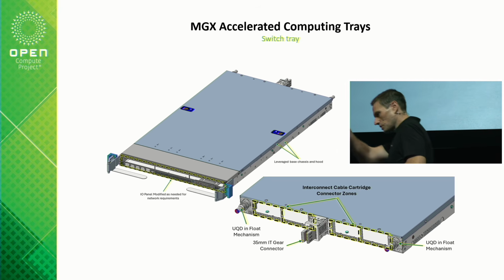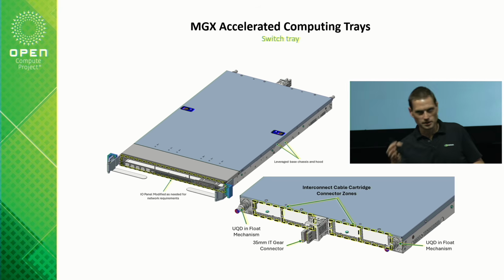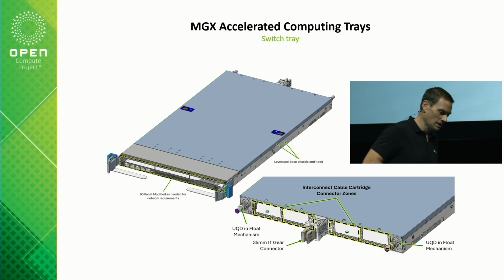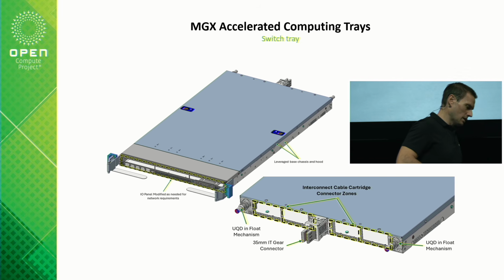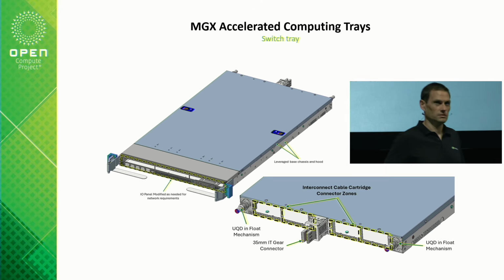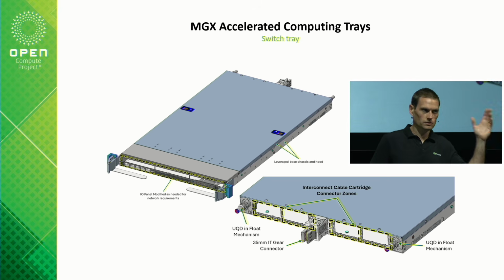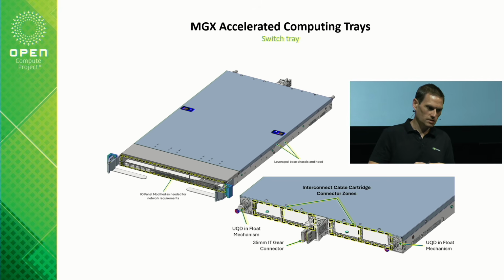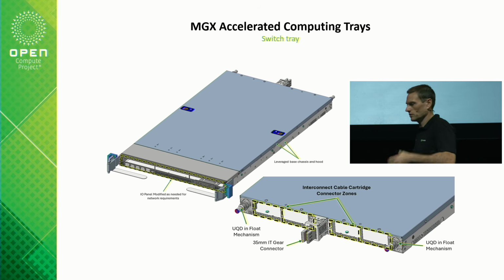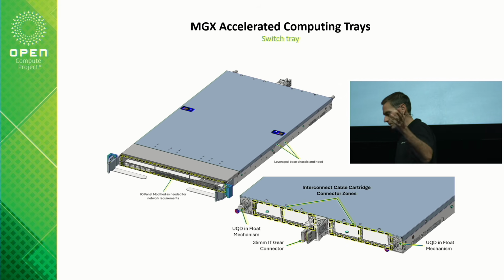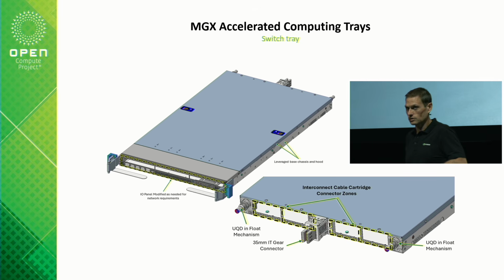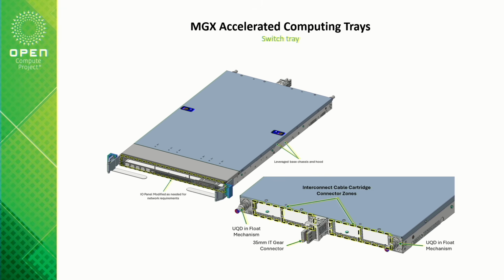I'm using the switch to illustrate this, and ironically, the switch in the lobby is a GB200 switch. That switch has no fans. That's one of the changes we made going from 200 to 300 — we wanted to capture as much of the power into the liquid loop as possible, so we were able to introduce a 100% liquid-cooled switch. You can go see that back there in the lobby.